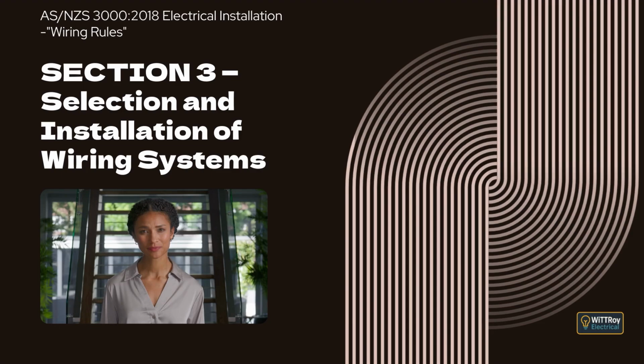Marker tape may be omitted for bored installations if the cable route is permanently recorded and, where an enclosure remains after boring, that enclosure is colored orange. Clause 3.11.4.6, Marking and recording of underground cable location.